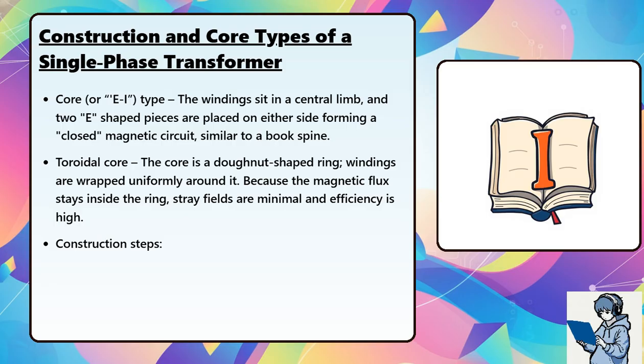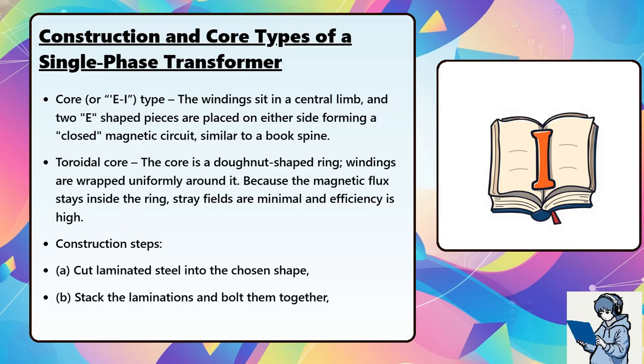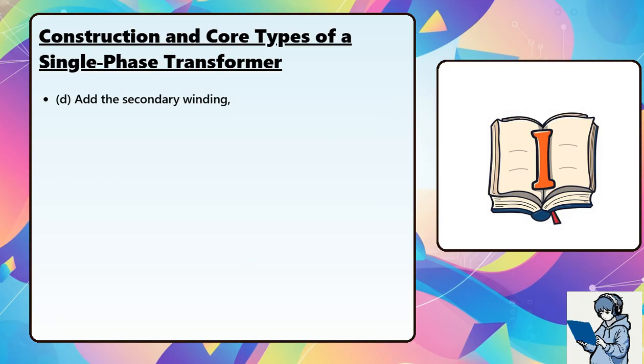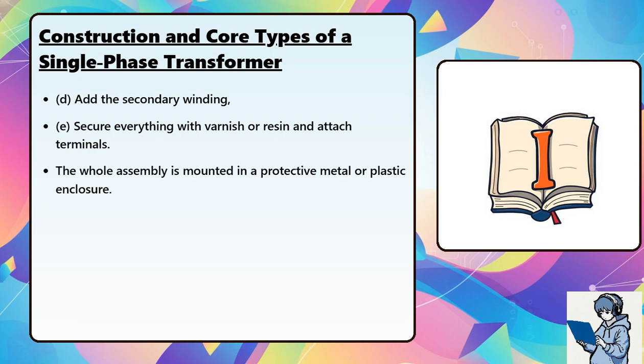Construction steps. A. Cut laminated steel into the chosen shape. B. Stack the laminations and bolt them together. C. Insulate the primary winding and place it on the core. D. Add the secondary winding. E. Secure everything with varnish or resin and attach terminals. The whole assembly is mounted in a protective metal or plastic enclosure.